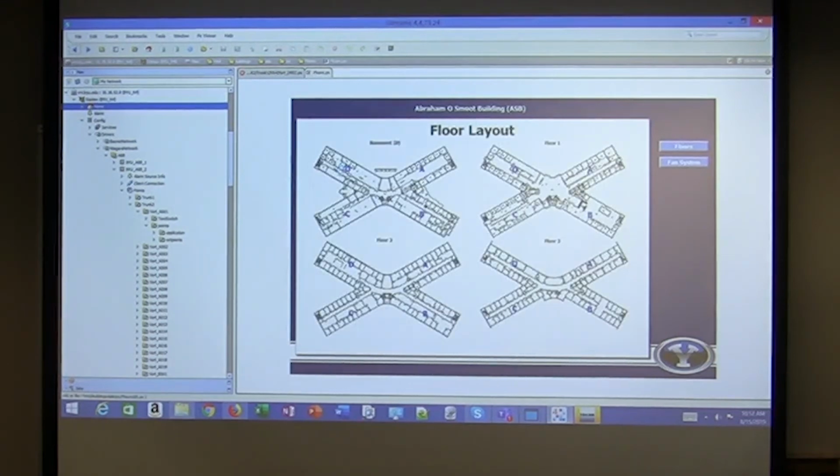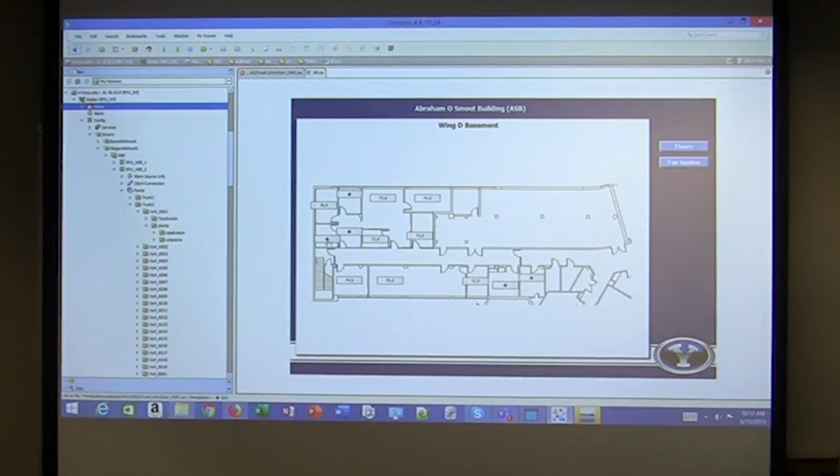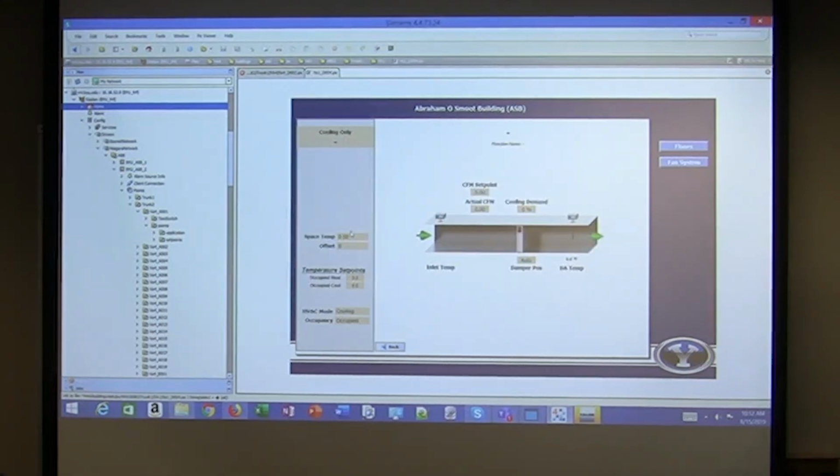Actually, before I leave that, what do these little question marks mean? It's not good. No bueno. So no handshake, right? It doesn't show yellow, but we know it's not communicating. That's an indicator that it's not talking to us. If I clicked on that point, is it just that the stat is not giving it a temperature? In this case, it's looking for temperature. In this particular one, if it's got a question mark, it doesn't have any kind of number coming in.